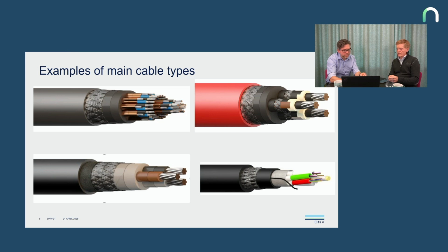Do all of the 606 cables have this braid, as on this picture? There are some without the braid. The four letters, for example RFOU, for the type are according to a table inside NEK 606. So this O is for the copper braid. So if you have an RU cable, that means there's no braid. So some few of them do not have the braid, like RU or BU if it's a fire-resistant cable. But I think most of them are armored types or braided types.